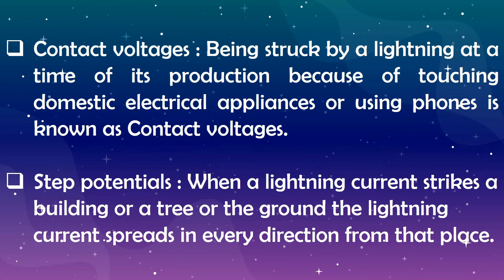Let's talk about step potentials. When lightning strikes the earth's surface, it spreads in every direction from that place. If you are near such an earthing point, you also get a shock because lightning enters through one leg and earths through the other. There is greater damage to cattle than humans in this phenomenon, because the distance between four legs increases the voltage difference across the body.